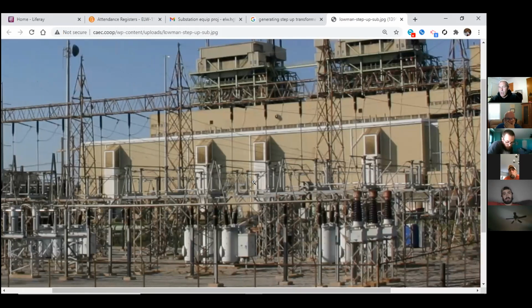A step-up transformer, and this is where you'll be using it, has to accommodate what the transformer is designed for. Think of this in the real world: generating typically will not go over 34,500 volts on the generator coming out to the step-up transformer. The reason is 34,500 or lower is much easier to insulate. So to get that from one point in the generating station out to the step-up transformer, that's a lot easier to insulate - your clearance distances could be lesser, and we don't have to have big structures to get that outside to the step-up transformer.